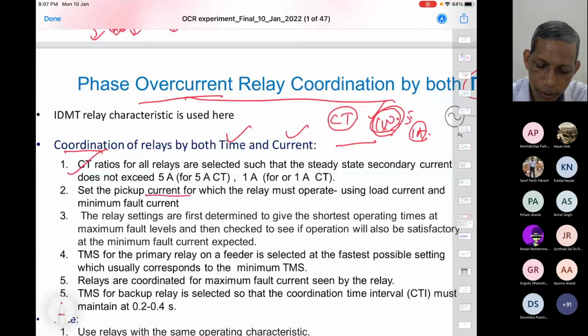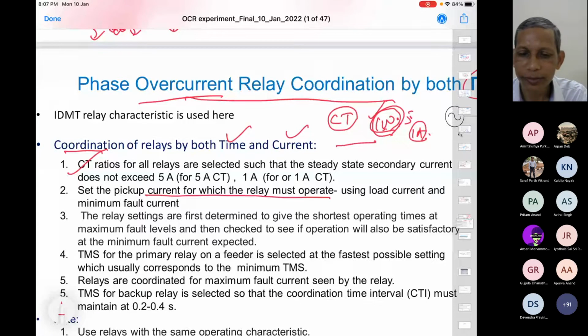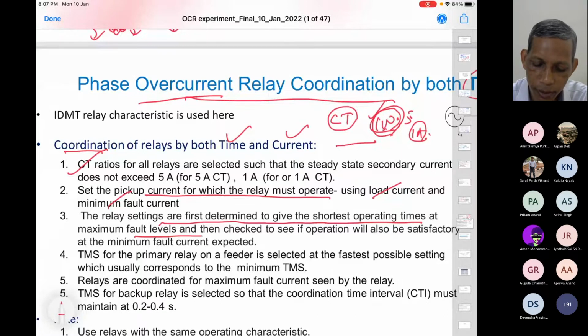Set the pickup current for which the relay must operate. We know it using the load current and the minimum fault current. The relay settings are first determined to give the shortest operating times at the maximum fault current levels, and then checked to see that the operation is also satisfactory with the minimum fault current.